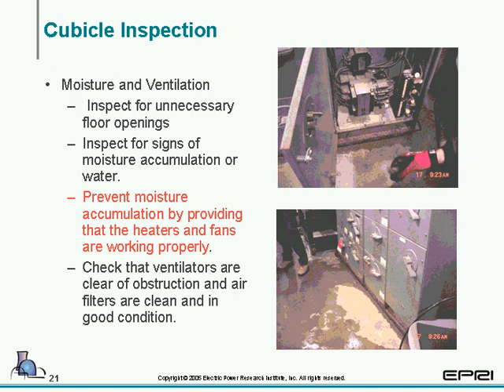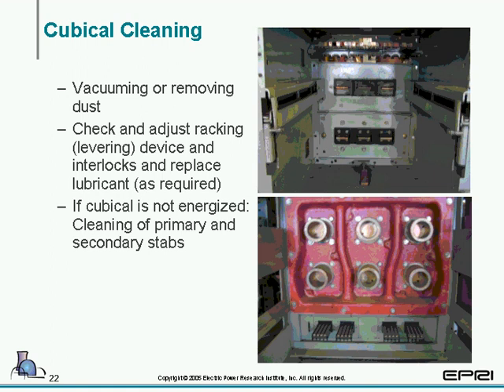And now, when you're doing your inspection, one of the things you want to take a look for is moisture and ventilation. You want to inspect for unnecessary floor openings, signs of moisture accumulation, and you want to prevent moisture accumulation by making sure that the heaters and fans work properly. And when we get into testing, we'll take a look at how to properly test or inspect them. And you want to check for ventilation, that it's clear and there's no obstructions. Cleaning. You want to vacuum or remove by brush or wipe down with a rag to clean any dirt, dust. You want to check and adjust any item that could not be checked or adjusted during the inspection phase. And again, do not work in a cubicle if it is energized.